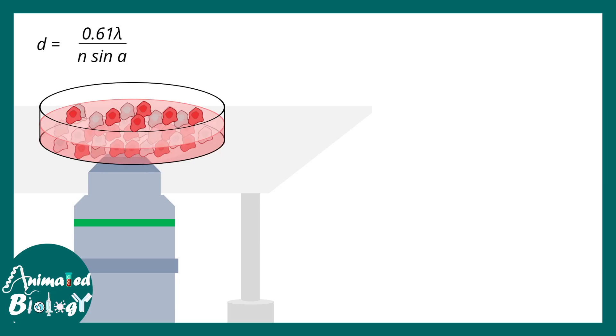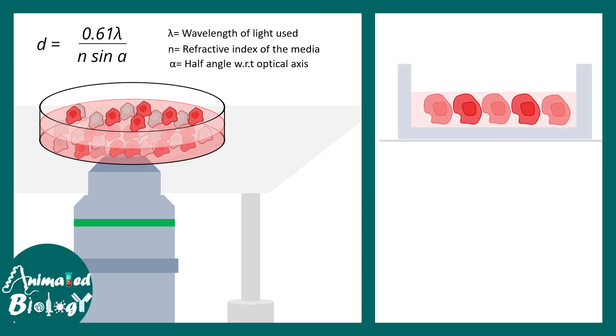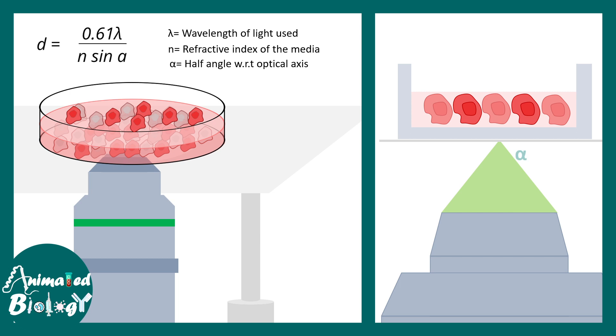Let us understand the terms. Lambda (λ) stands for the wavelength, n stands for the refractive index of the media, and alpha (α) stands for the half angle with respect to the optical axis. Looking at the image of an objective imaging cells, the wavelength used is green light and alpha is the half angle with the optical axis. In this case it's an oil immersion objective, so n is the refractive index of the immersion oil.